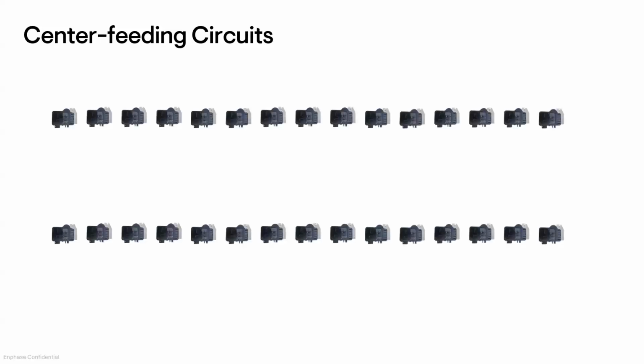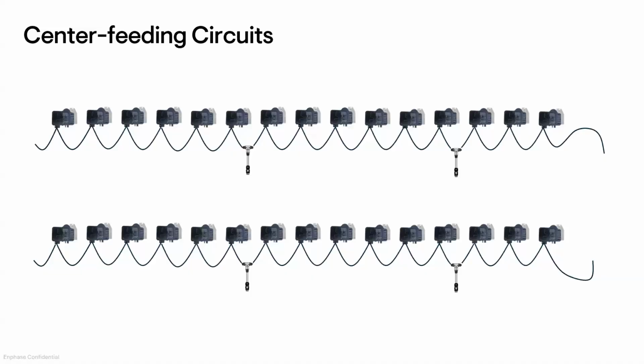I'm going to take a little bit closer look at that holistically and see what that looks like when we build a full circuit of 30 IQ9s. So there's 30 IQ9Ns. For this example, it's hard to fit 30 all in a row, so I have 15 in one row, 15 on another row. We're going to grab our QD cable and plug it into each microinverter on each row. We're going to install our terminators at each end to safely seal and cap off the QD cable. We're going to use male and female field wireable connectors along with raw QD cable to make a jumper. So now we've completed a full circuit of 30 microinverters in that circuit. And as you can see, there are 4 center taps in this fully loaded circuit. That gives you the flexibility and option to choose the one that works best for you.